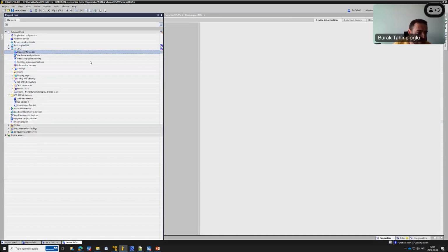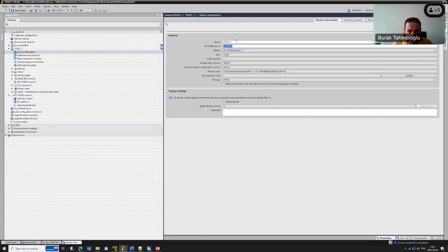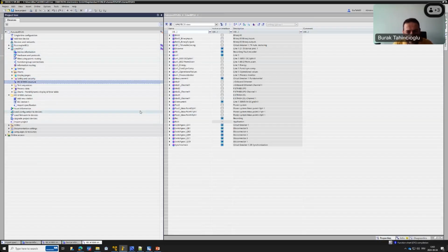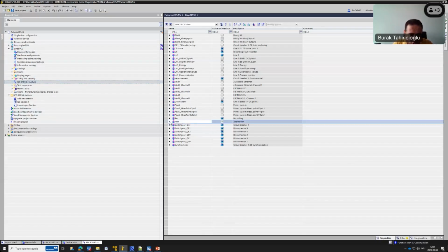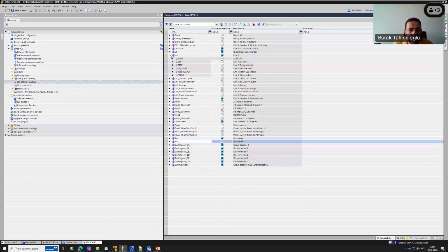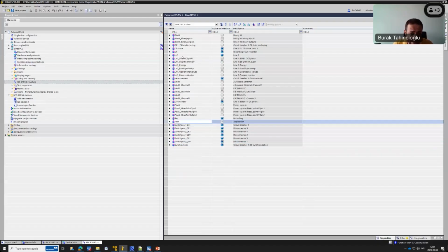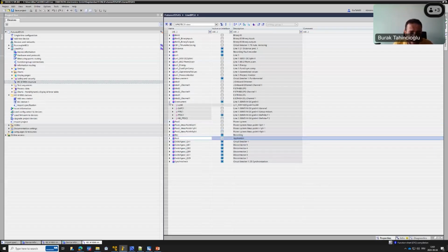And for the line, if you continue, here I see the name is taken over by DIGSI, and I want to see the structure, which is the data model of it. I see it's again a good adaptation of the data model. Even the root is defined, the LPHD is there, but you see one additional checkbox, that's the line. That's just because Siemens wants to add it due to the functions of the SIPROTEC 5 devices. You cannot have a protection function without having the line logical device, but there will be no communication of it, so you see it's only LLN0. You have to do this because of the design, but the rest is actually what I have defined.